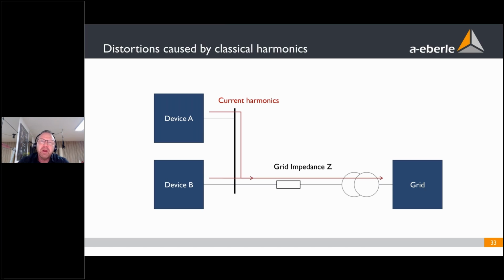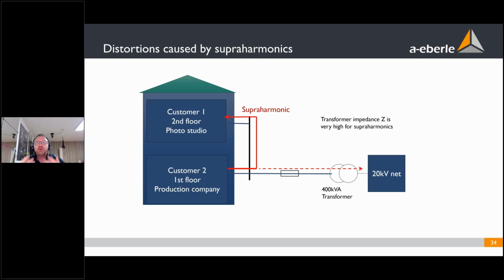So normally, if you have different customers producing harmonics over the current going over your cable to the transformer, most of the harmonics the transformer will transfer to the medium voltage network. Even in the medium and high voltage network, you will find the 5th harmonic, the 7th harmonic. So all the disturbances we normally produce mainly on the low voltage side. With supraharmonics, this is absolutely different.